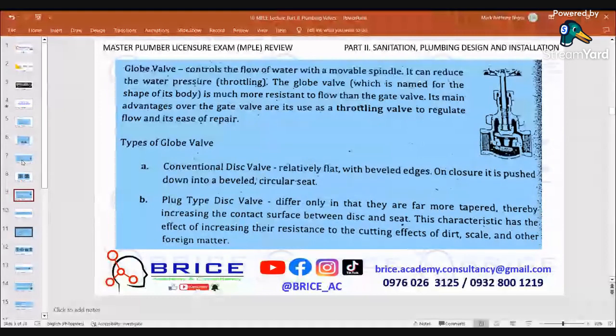Letter A, conventional disc valve, relatively flat with beveled edge. On closure, it is pushed down into a beveled circular seat. Letter B, the plug type disc valves differ only in that they are far more tapered, thereby increasing the contact surface between disc and seat. This characteristic has the effect of increasing their resistance to the cutting effects of dirt, scale, and other foreign matter.